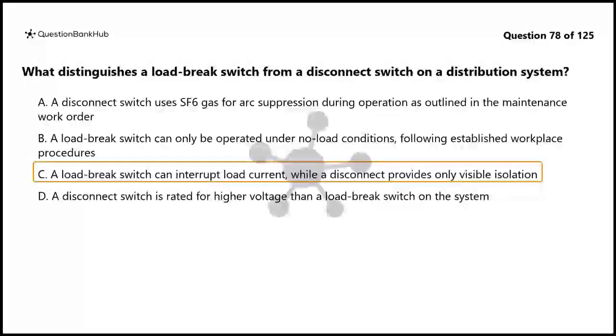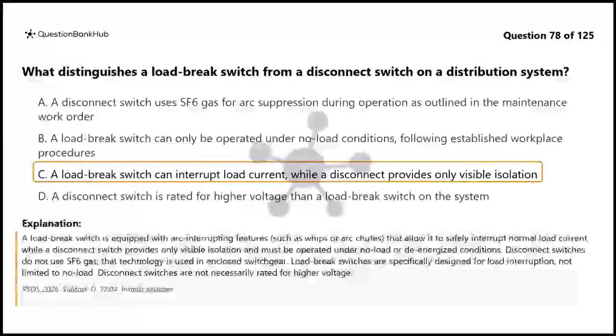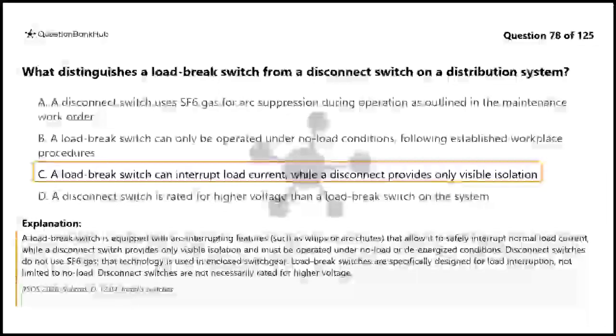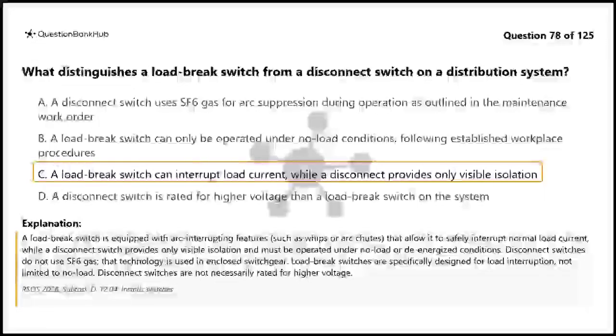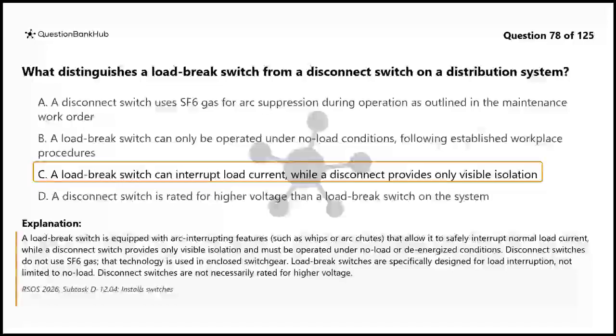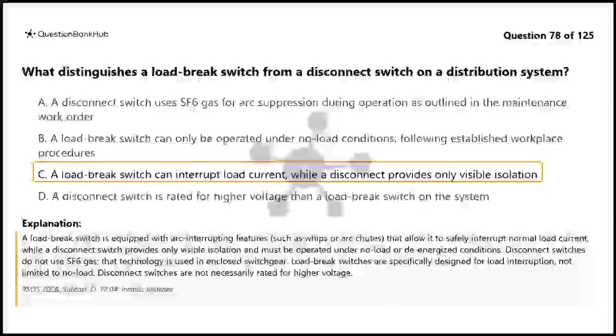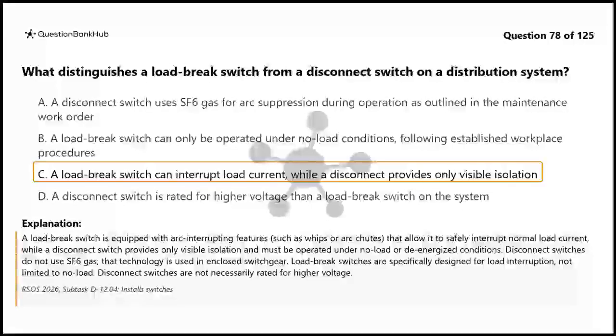The correct answer is C. A load break switch is equipped with arc interrupting features, such as whips or arc chutes, that allow it to safely interrupt normal load current, while a disconnect switch provides only visible isolation and must be operated under no load or de-energized conditions. Disconnect switches do not use SF6 gas. That technology is used in enclosed switchgear. Load break switches are specifically designed for load interruption, not limited to no load. Disconnect switches are not necessarily rated for higher voltage.